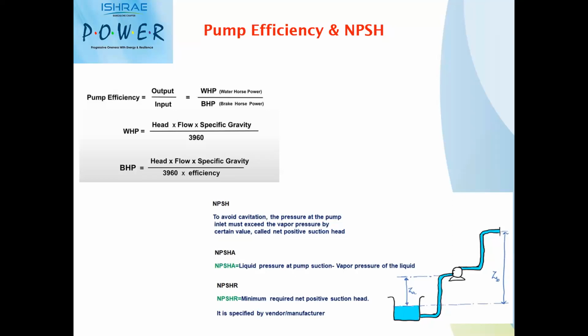When it comes to cooling tower pumps, say for example the cooling tower is on the terrace and the pumps are in basement one. The suction pressure exerted by the water column built from your cooling tower exit to the pump suction is called net positive suction head available. In a typical sketch I have shown here, it is the sump, and then this is the suction of the pump.